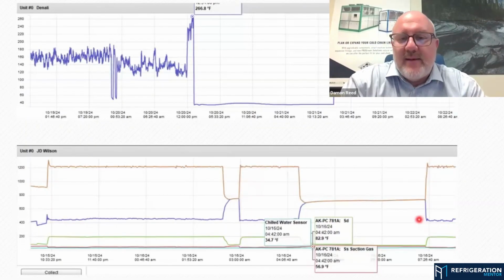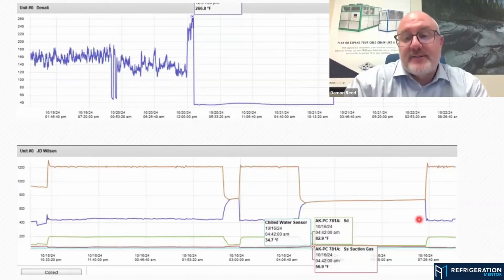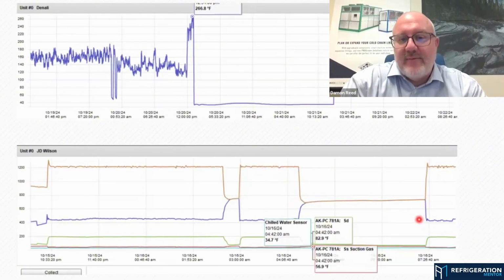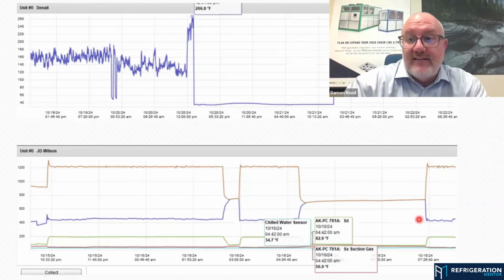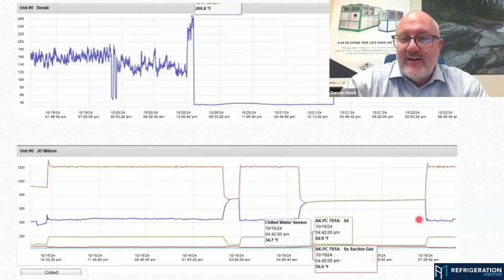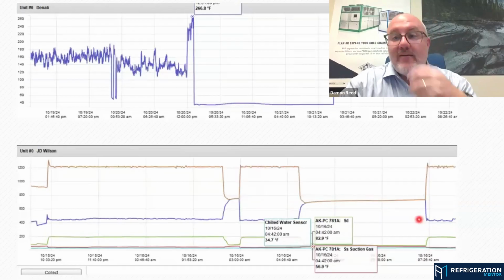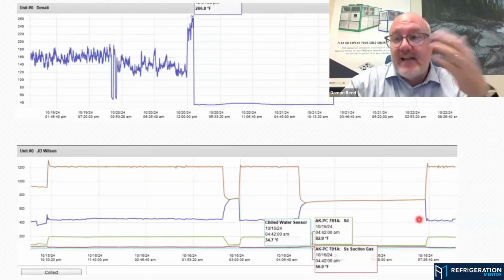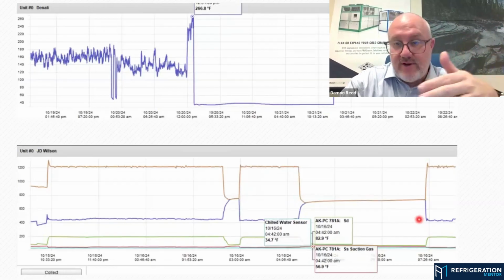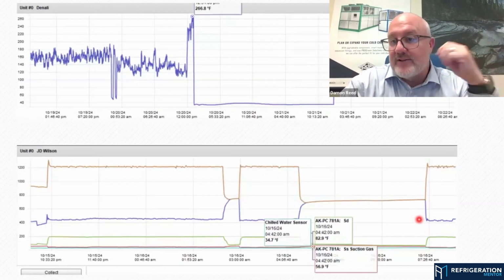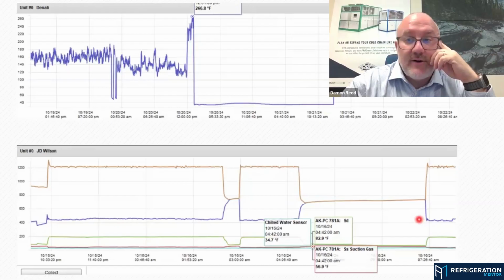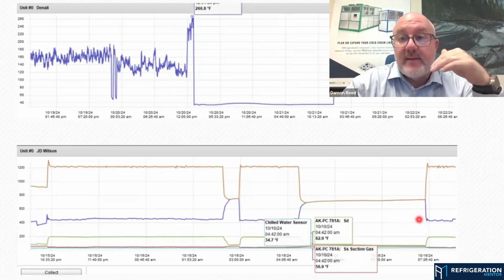This was an example where we had a bad discharge transducer. This was actually one where, when we were doing the diagnostics, we couldn't identify remotely any reason for there to be an alarm. The system was going off on a compressor safety alarm, which was traced back to the high-low pressure switch. We were able to talk with a maintenance mechanic on site who was able to reset it.